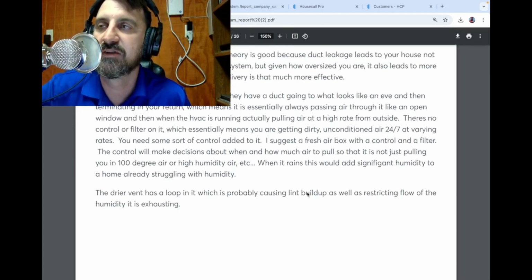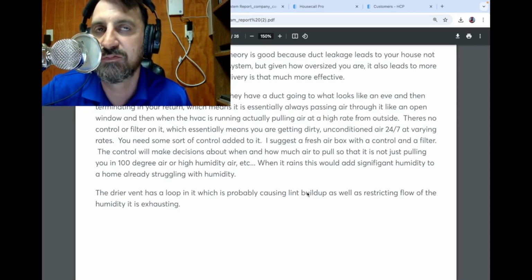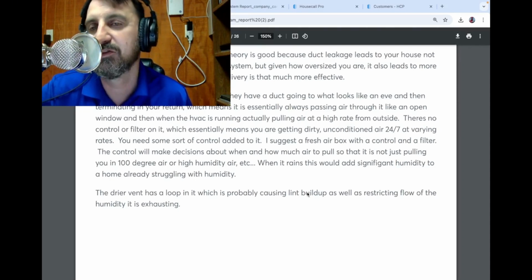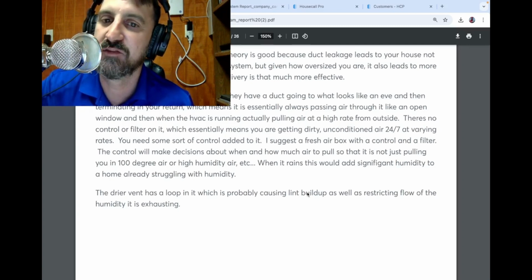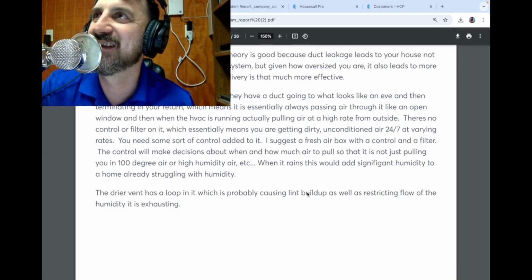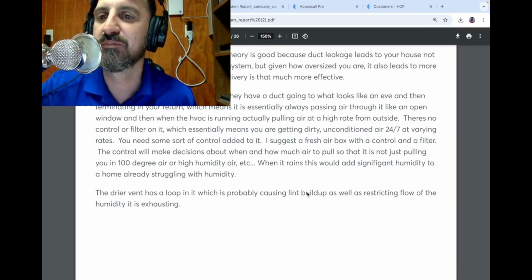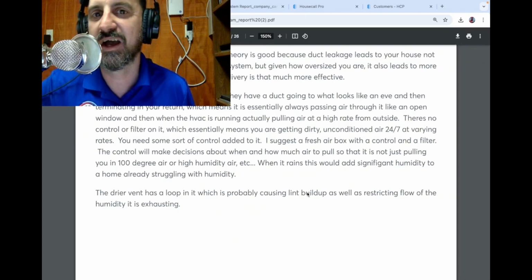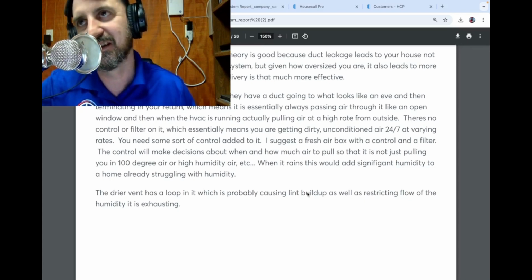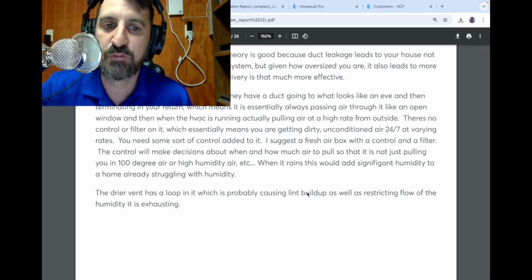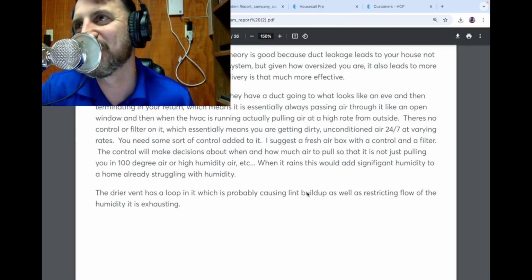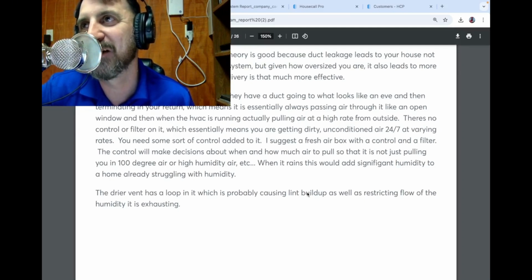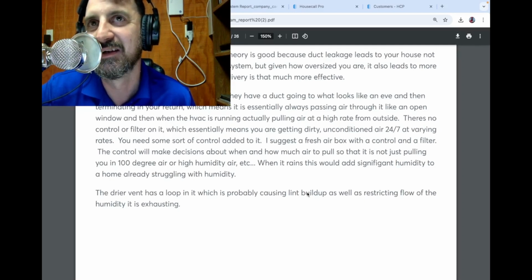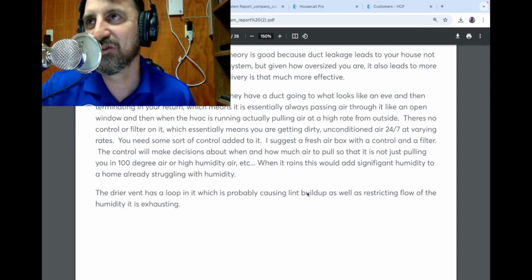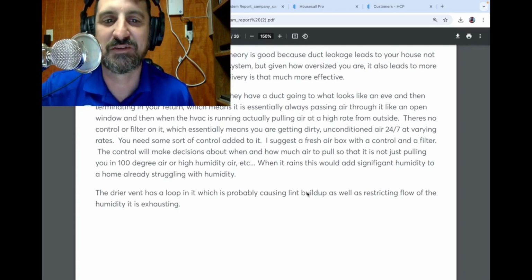Mixing that 105 degree air with the air from your home, this one was running 69 degree air in the home, but the humidity was so high that it did not feel like 69. But you're basically mixing that 105 and that 69, which is adding to the humidity because you're adding heat to cold air. If it's raining outside, it's even worse because then you are pulling in air that is essentially rain from outside, and then adding the problems of moist air and dirt and everything mixing together.